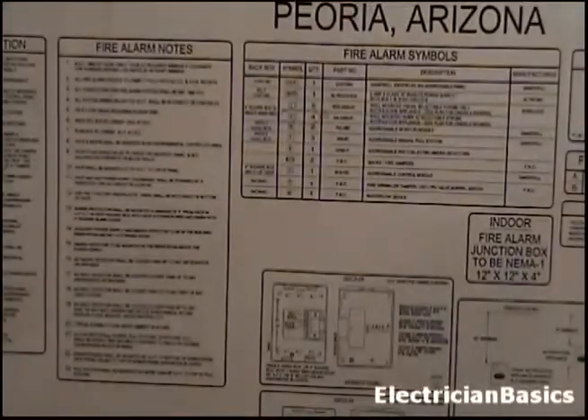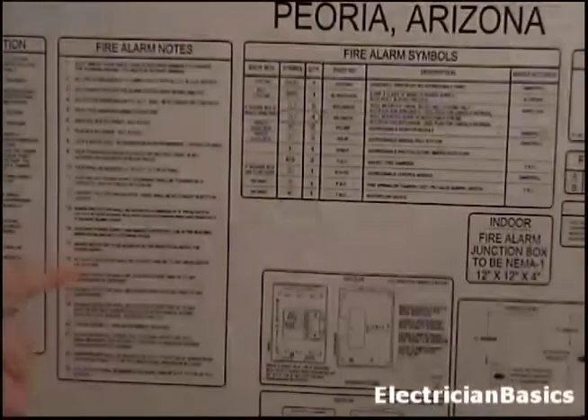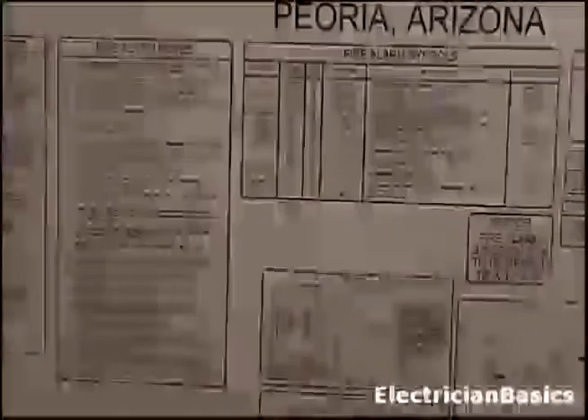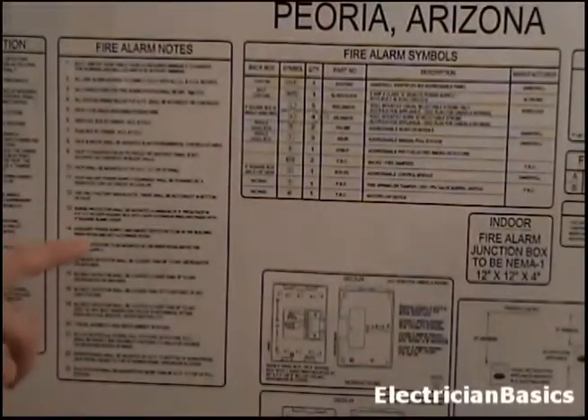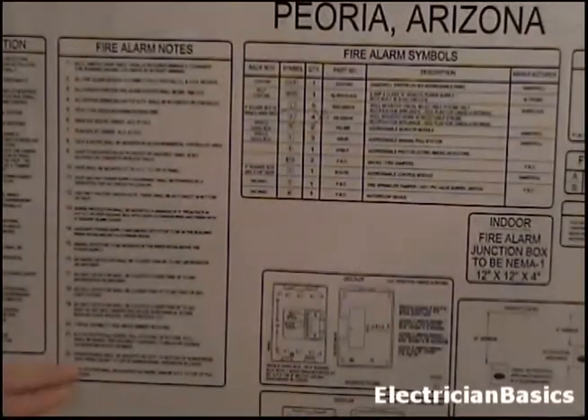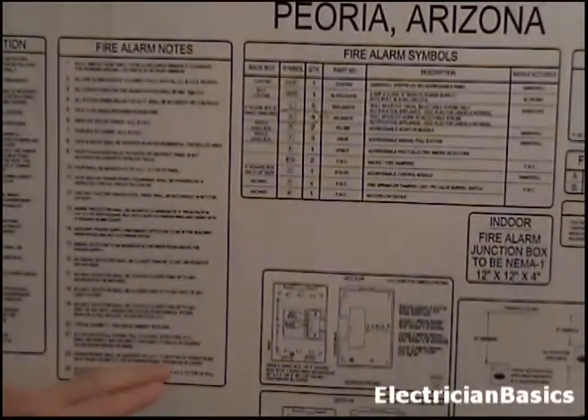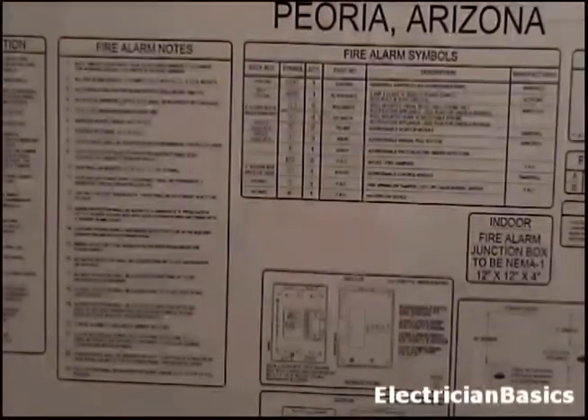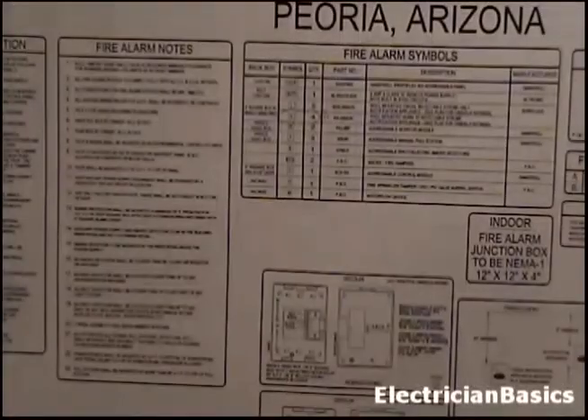Now we can find the locations of these things on the reflected ceiling plan, and also on sheet M1.1 we can find where all these registers, diffusers, and things like that are. So when they lay out the locations of these devices, you have the ability to move those slightly so that you don't get them too close to any one of these. Okay, let's look at note 22 because we have something important here. Horn strobes shall be mounted 80 inches above finished floor to the bottom of horn strobe, or 6 inches from ceiling to top of horn strobe, whichever is lower. On the other notes we said things should be mounted to the center unless otherwise noted. Well, who makes the determination?